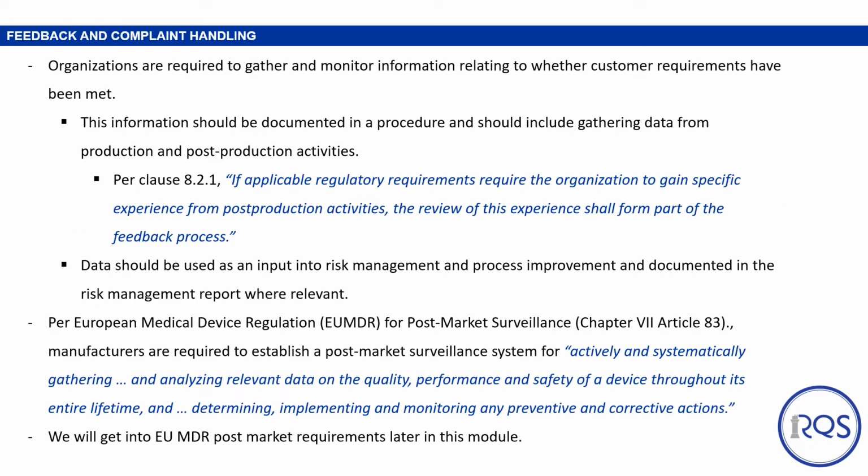Organizations are required to gather and monitor information relating to whether customer requirements have been met. This information should be documented in a procedure for the feedback process and should include gathering data from production and post-production activities, as mentioned in Clause 8.2.1. This data should also be an input into the risk management and process improvement processes and documented in the risk management report where relevant.